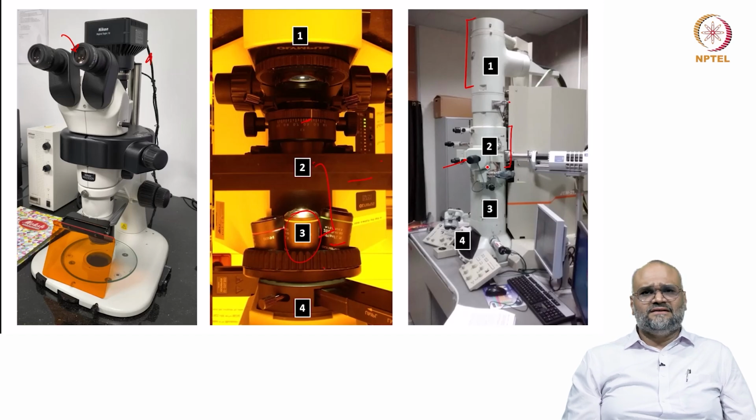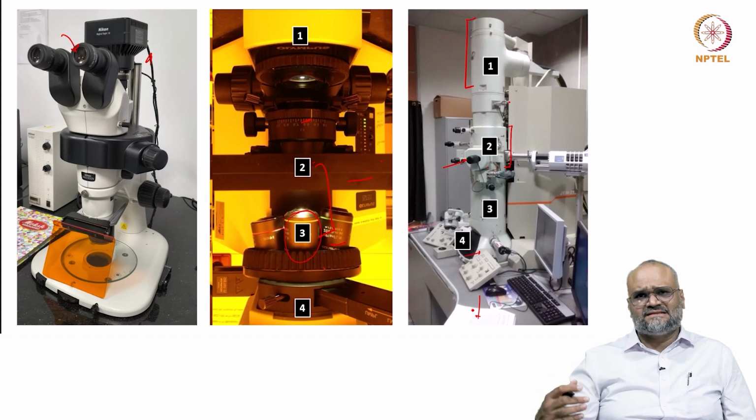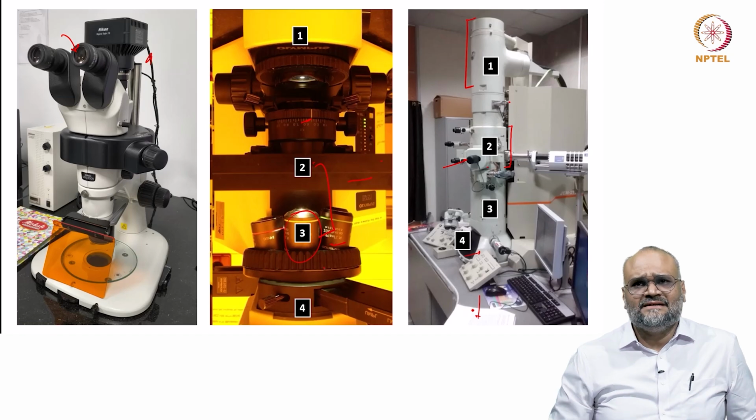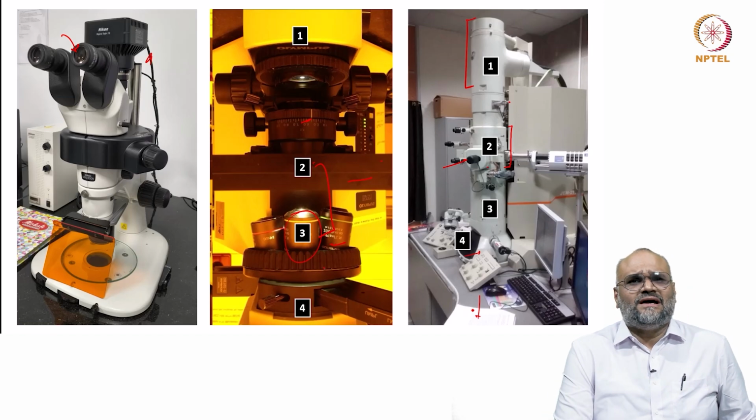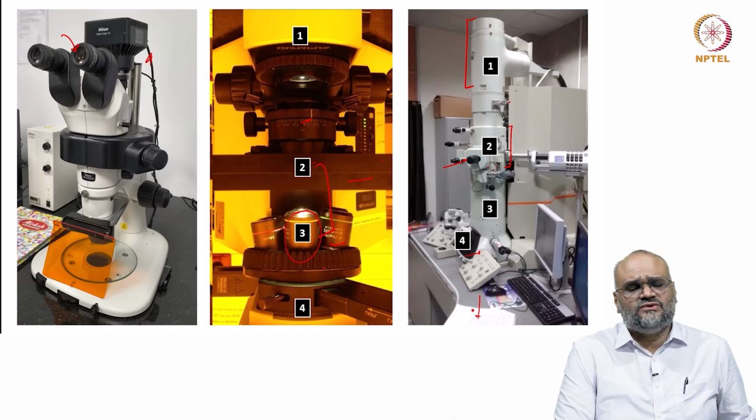And next we have the detection system. You typically use a CCD camera. You can see the image formed on the fluorescent screen here, which is behind this number 4. The fluorescent screen is somewhere here, and then the on-axis or off-axis recording cameras are below the microscope column. So this is the general layout of the microscope, and then we started understanding each of the components one by one in this kind of a sequence, the way in which they are arranged in a classical upright transmission electron microscope.